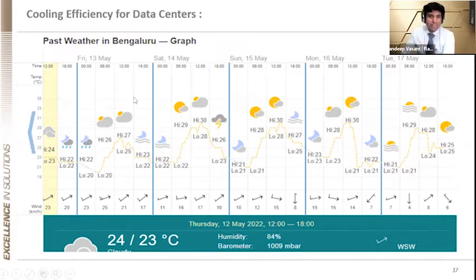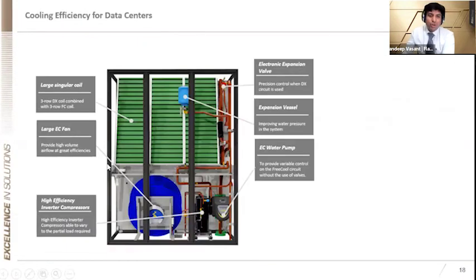I live in the city of Bangalore. For the last 3 weeks it has been raining and the temperature is close to Shimla, close to 23 degrees. We can practically get the air inside. Obviously, we need to filter it, but there are chances that we could get direct free cooling done. If not, if the ambient conditions are very harsh, in most cities like Delhi, I keep seeing articles that there is a heat wave going on. Nevertheless, we can use indirect free cooling equipment.